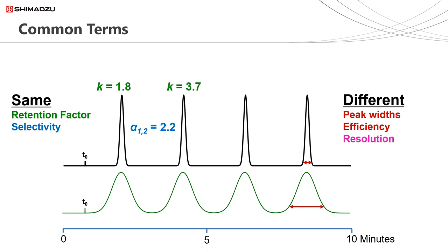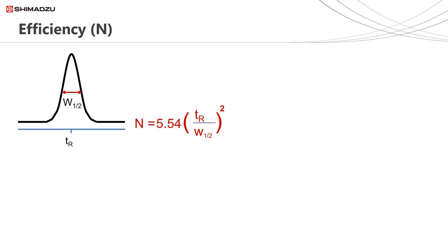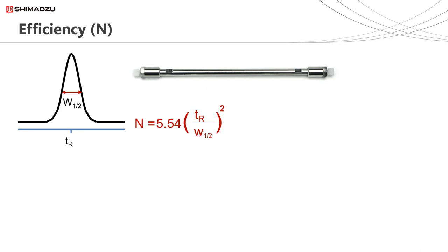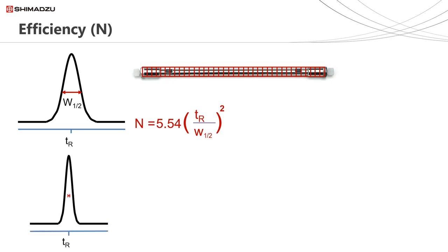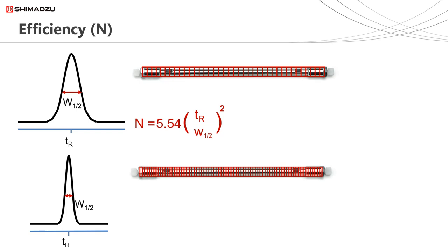Peak width affects efficiency and also resolution. Efficiency N can be calculated using this equation. What we need is a value for the retention time TR and the peak width. This particular equation uses the value for the peak width at half height, but other equations use the peak width at 10% height or the tangent width. The value this equation gives is the number of theoretical plates for the column which generated the peak. If we now look at a narrower peak eluting at the same retention time, then the efficiency N, or the number of theoretical plates in this column, is higher.